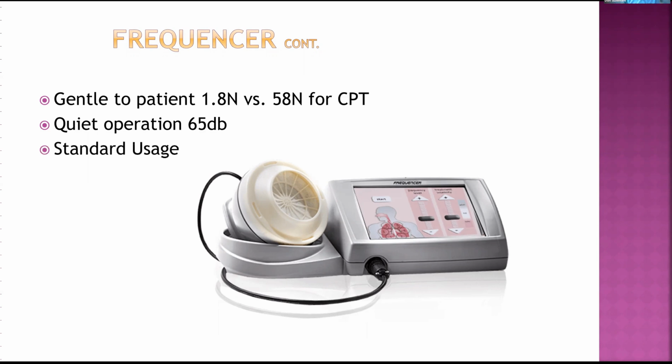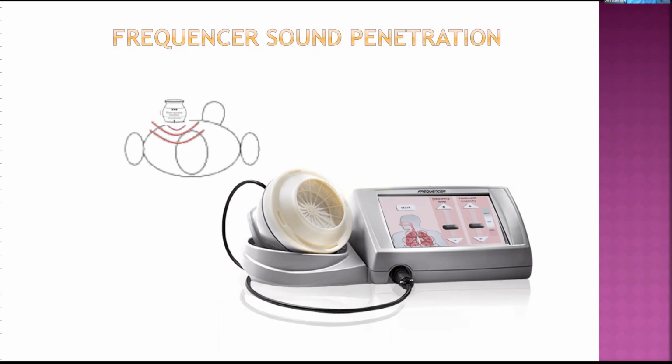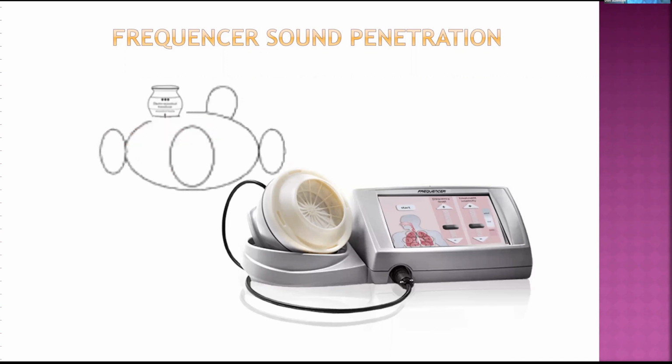Standard use of it, as I mentioned, is to put the transducer on the patient and seal it. A towel or a thin cloth, a t-shirt, works well between the patient and the transducer. Where we put it on, it could cause a little red ring that does nothing. It goes away just seconds after you take it off. But the t-shirt or towel prevents that, and it still directs the sound into the body.